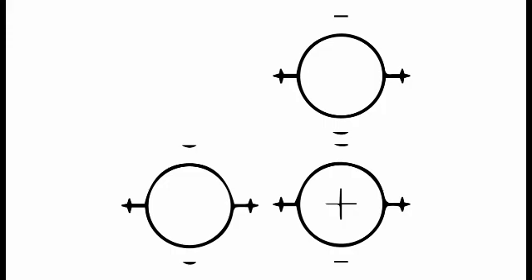It is important that the cross in the eyepiece is near the centre of the focusing circle — at this point, the optic axis of the instrument will coincide with the visual axis of the patient's eye. Focusing is accomplished more precisely by the overlapping of the focusing circles appearing single. With an astigmatic eye, all central focusing circles will not appear exactly in focus at the same time — for greater accuracy, direct attention to the double plus sign and focus it sharply. The focus of the minus sign is disregarded until later.